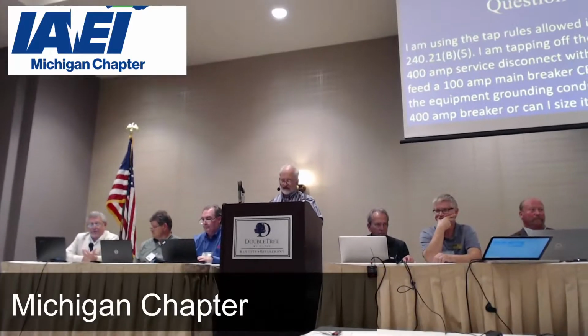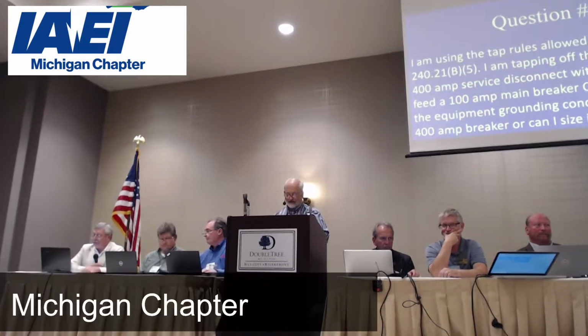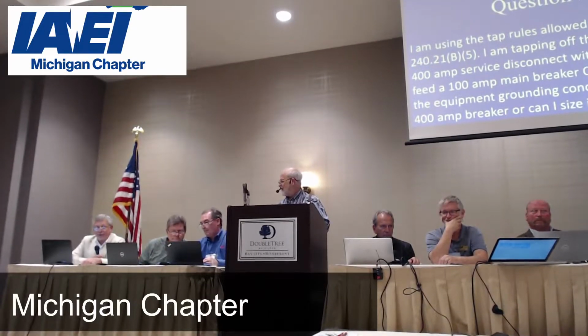I'll be retired by then, so. What I was saying is picture the 400 amp here and picture the 100 amp down here, and a fault in between the two. The conductors that are carrying that fault are the 100 amp tapped conductors, right? So the 400 amp conductors feeding the 400 aren't my circuit conductors in that case. In which case I would have larger conductors tripping that 400. Once I change to the smaller ones, those are my circuit conductors for my fault, right? Yeah, but they could be tapped, I mean, it could be a number 8 tapped off of a 4/0, so you still have a lot of fault current there. It's a great question, and I think maybe it needs some clarification.